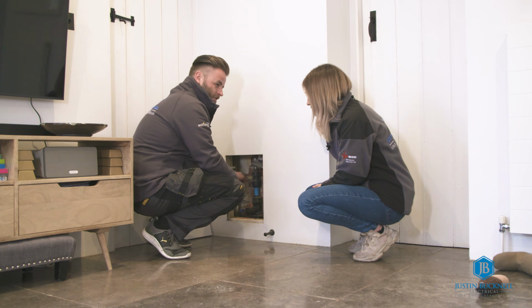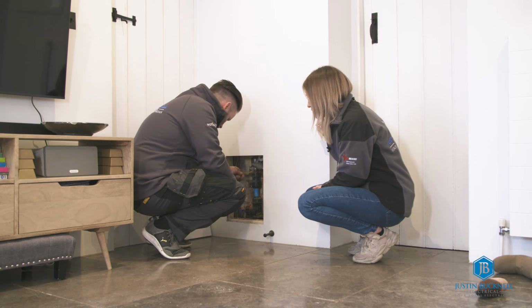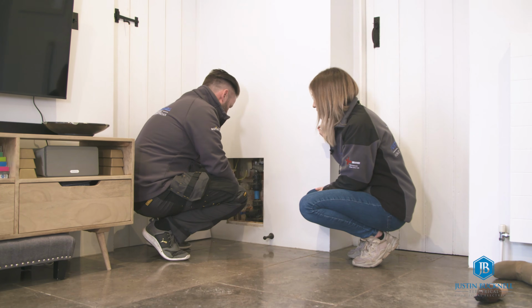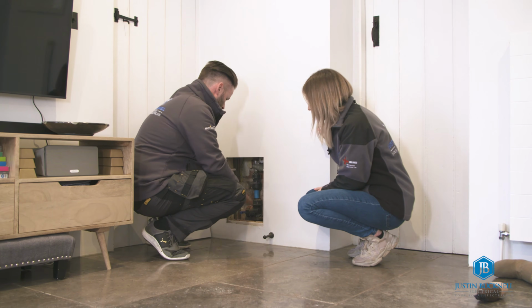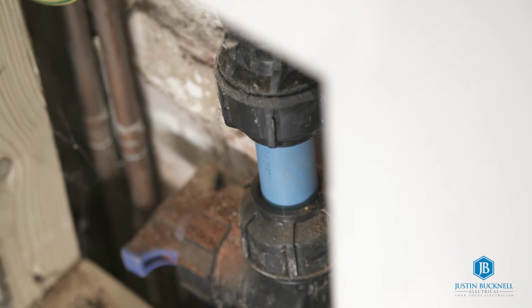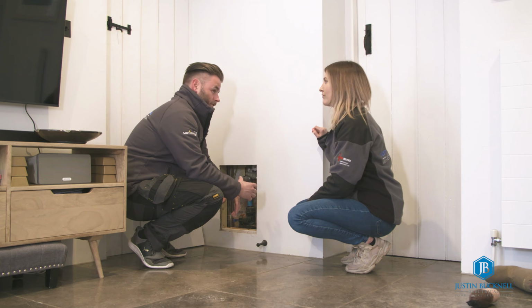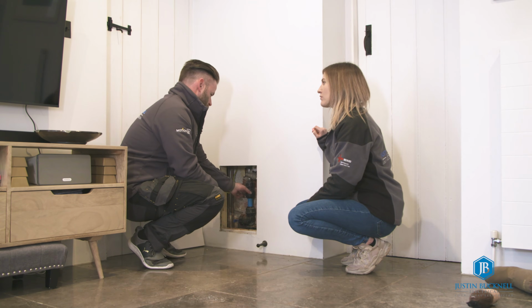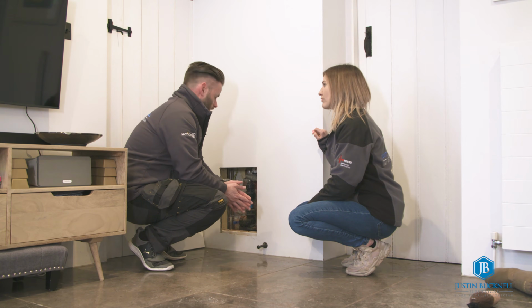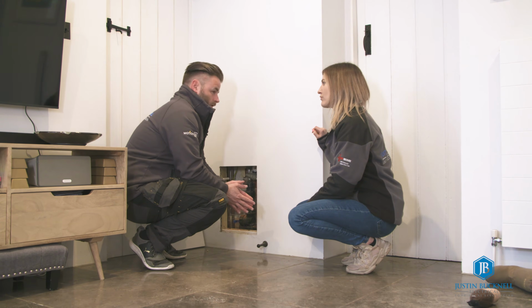However, the previous electrician seems to have run a cable in here which is not connected to anything, because there's nothing to connect to, because it comes in as plastic and it continues as plastic through to another part of the system there. So on the electrical installation condition report, we'll mark the box for water bond as NA, non-applicable, because this system doesn't need the water to be bonded.